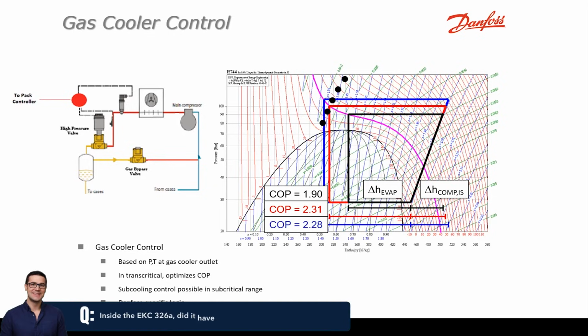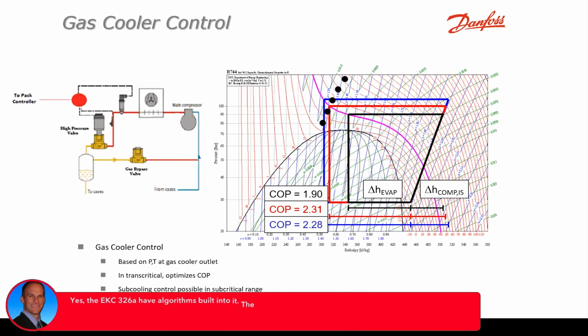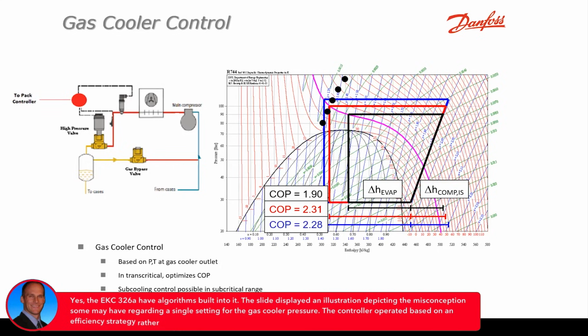Inside the 326A, did it have those algorithms built in already? Yep. And that's what you see on the slide to the right here. The guys may think that there's one setting for the gas cooler pressure, and it was more of an efficiency strategy, where we don't always want to shoot for the same pressure coming out of the gas cooler at any point in time. And that's where the sensors also become very important.